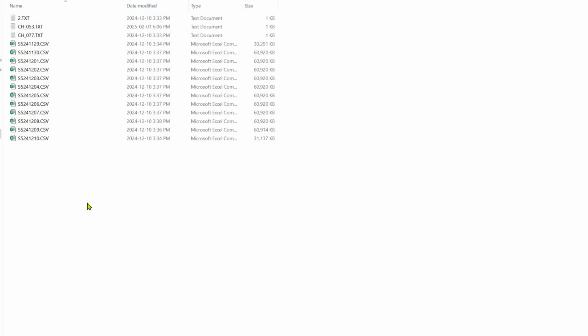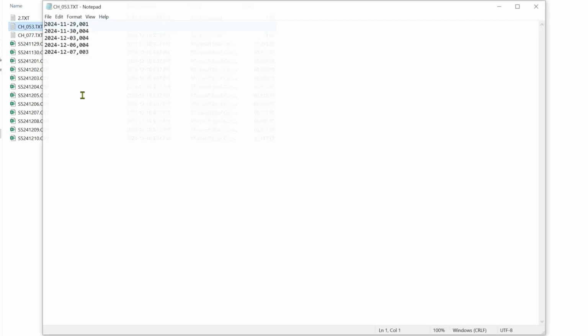Most of the cases, data loggers are used to catch some randomly happening issue with the system. This recording is about 2 weeks, and some error codes happened during the period of recording. This site has some problems with electricity and was really windy on site. So we had the communication error CH53. It is when the indoor units are disconnected.